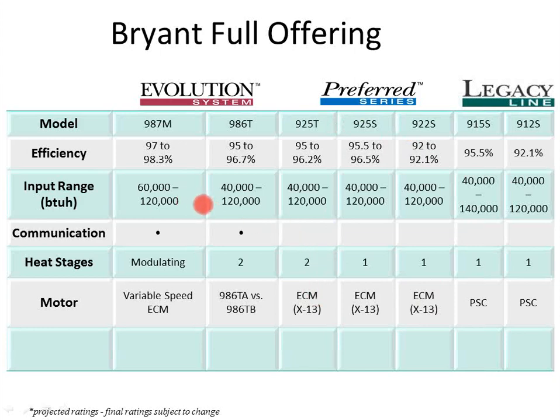On the Evolution side, there are actually 2 furnaces, the 986T and the 987M. The 986T is in the middle of a transition, just so you know. It was 986TA. The new one is 986TB, and the only real difference is that it's switching from a non-communicating variable speed motor to a fully communicating variable speed motor. Previously, you were not able to use the 986TA with Evolution zoning systems or for dirty filter pressure drop sensing. The new 986TB eliminates that problem, and now you can use it in all Evolution applications.